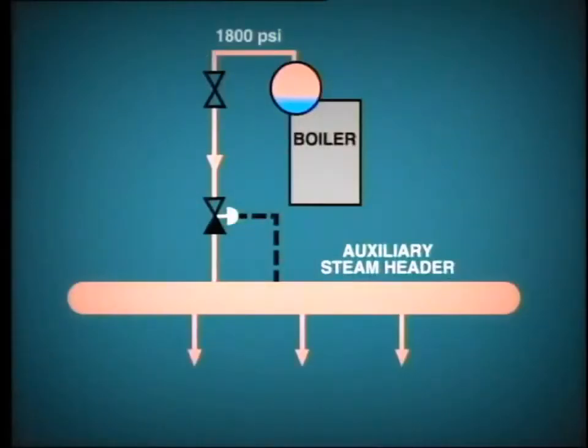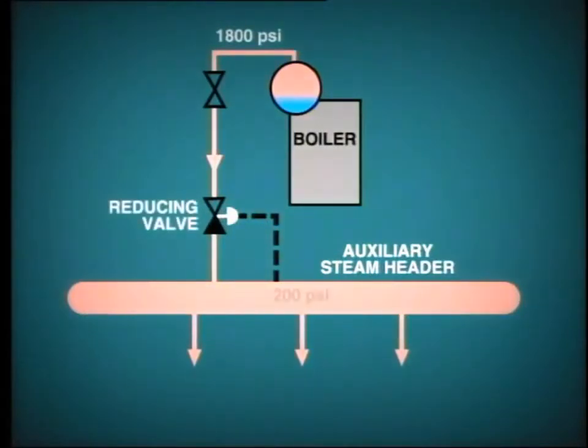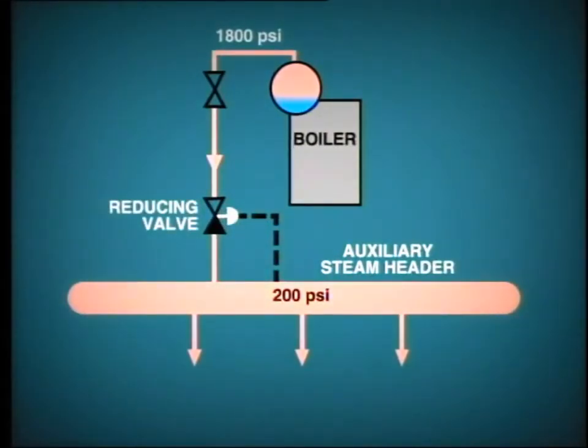So what other sources may be used to supply auxiliary steam? One common method is to use saturated steam from the boiler drum. This feeds through a reducing valve to provide steam at about 200 psi on the auxiliary steam header.